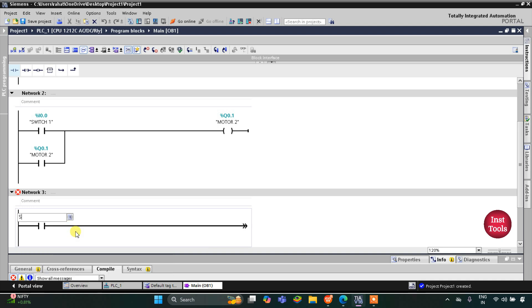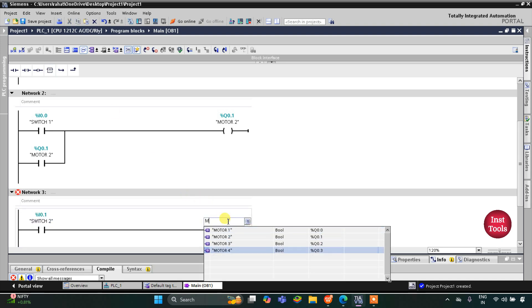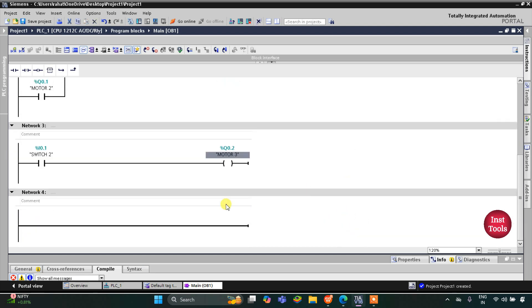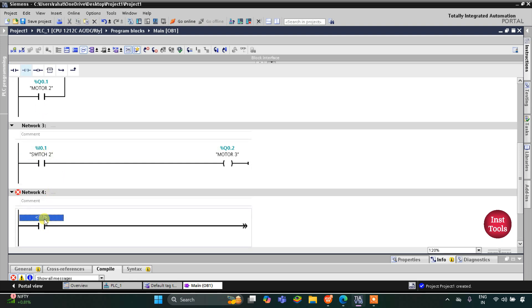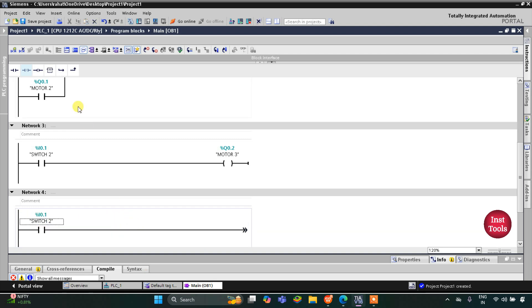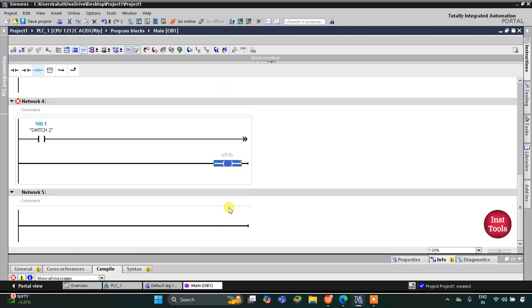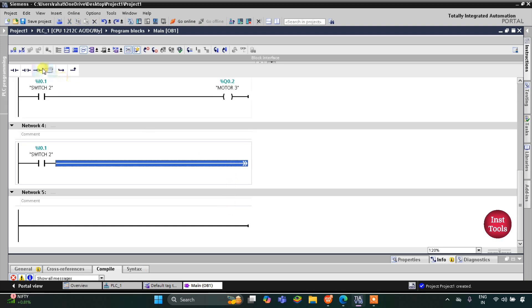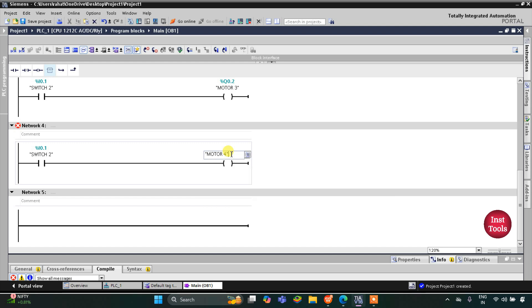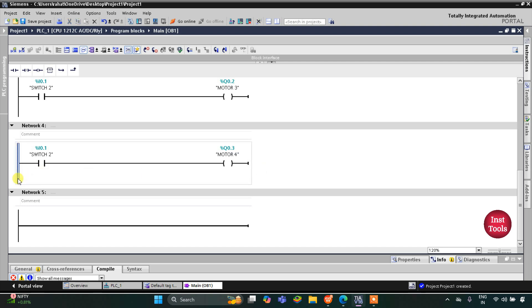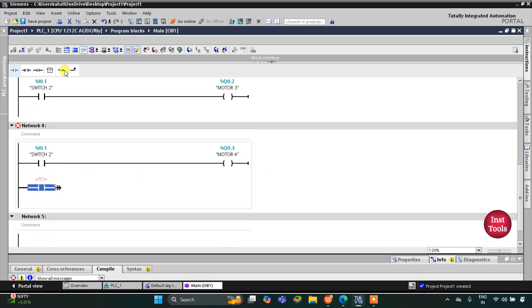For Switch 2 I will add a normally open contact and then a coil for Motor 3. So when Switch 2 is turned on, Motor 3 gets on. Then Motor 4 should also get on, so I will insert Switch 2 as a normally open contact and then a coil for Motor 4. When Switch 2 is turned on, Motor 3 and Motor 4 get on. For Motor 4 to remain on when Switch 2 turns off, I will open a branch, add a normally open contact, and close it — assigning the same address as Motor 4, which is Q0.3.